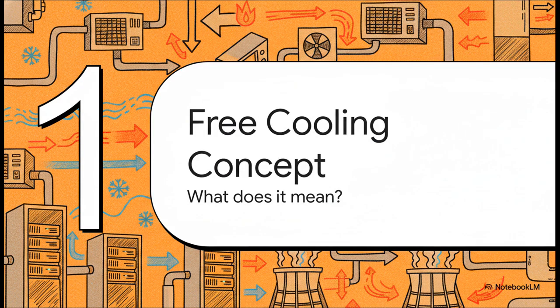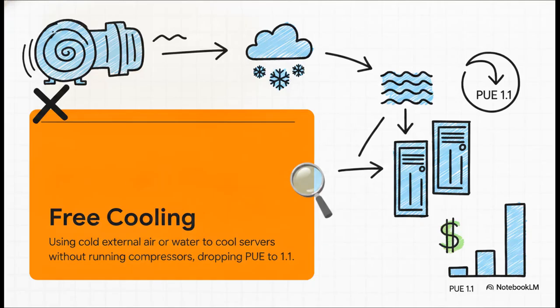What does free cooling actually mean for a high-tech facility? So in a standard cooling system, the compressor is the heart of the whole operation. It physically squeezes refrigerant gas to reject heat, and honestly, it consumes a monstrous amount of electricity doing it. Free cooling is the clever engineering trick of just bypassing that compressor entirely. By using naturally cold external air or water to do the chilling, these facilities basically get their cooling energy for free, and the result? It drives a vital metric called power usage effectiveness, or PUE, down to an incredibly efficient 1.1 or 1.2. That basically means almost every single watt of power entering the building goes directly to the servers, not to the air conditioning.